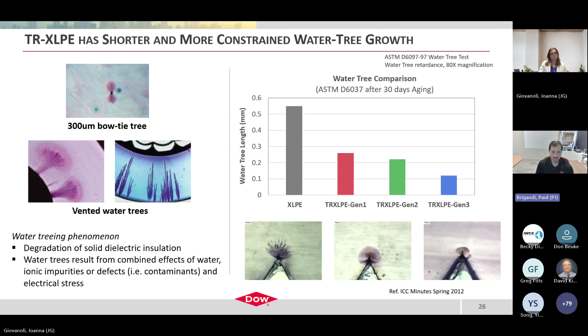We had a very unique opportunity to pull some cables out of the ground along the course of 40 years. This past couple years has marked the 40-year period for tree retardant XLPE and EPR cables in the field, where they were designed and expected to last for 40 years, but nobody really knew what would come of it. We had this unique opportunity at the Galleria Mall working with Alabama Power. When the first generation of materials were installed around the 1984-85 timeframe, the mall actually opened in 1986, so we were able to remove cables along with Alabama Power and do some diagnostic testing on these materials.